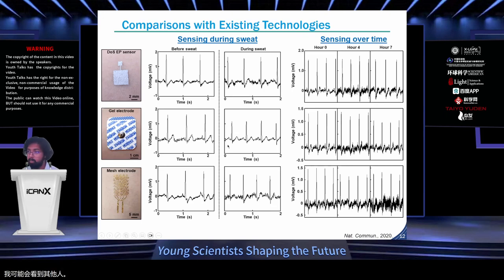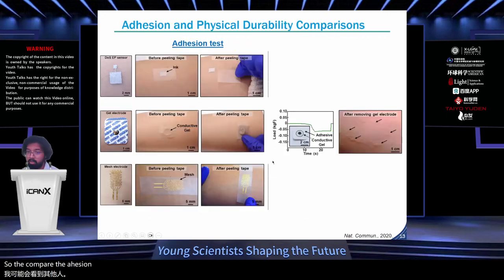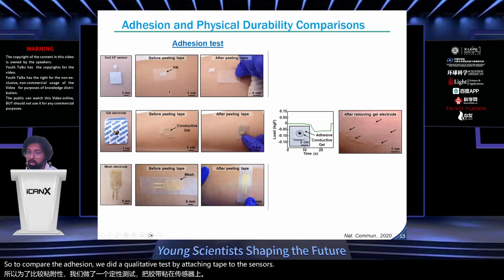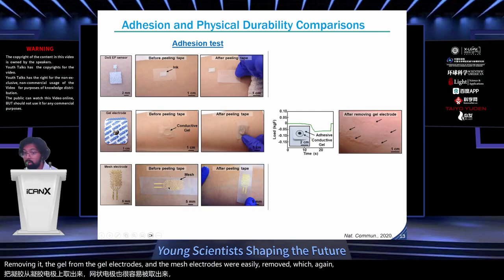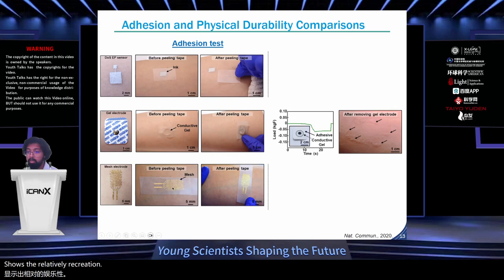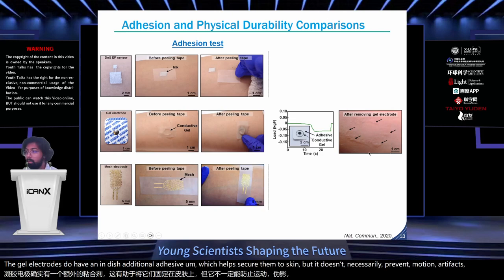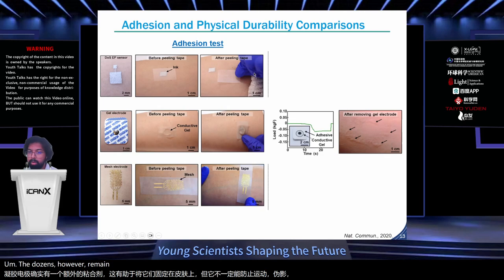To compare adhesion, we did a qualitative test by attaching tape to the sensors and removing it. The gel from the gel electrodes and the mesh electrodes were easily removed, showing relatively poor adhesion. The gel electrodes do have an additional adhesive which helps secure them to the skin, but it doesn't necessarily prevent motion artifacts. The DOS sensors, however, remained pretty much intact after this.